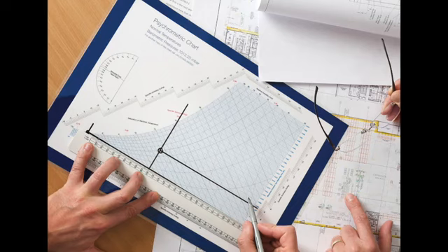Yeah, that's right. And to figure that out, we need to perform a psychrometric calculation. And we do that using a psychrometric chart. A psychrometric chart shows the relationship between air temperature, relative humidity, and air's physical moisture content. These three characteristics of air are intimately linked together, and changes to one impact the other two.